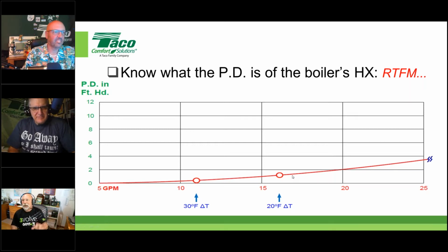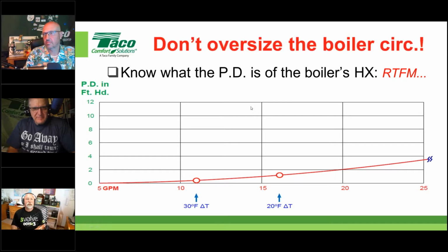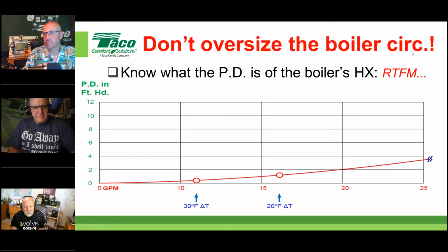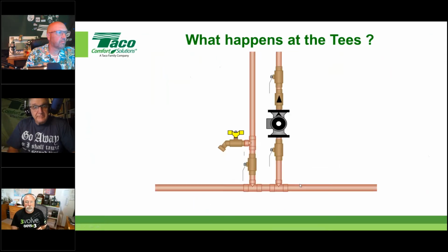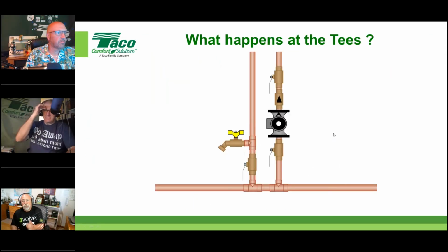There's all kinds of them out there, but what I want to emphasize more than anything is don't oversize the boiler circulator, and this is how you're capable of not doing that. You have to know what the resultant pressure drop is at given flows throughout the boiler's heat exchanger. So if you don't follow that, let's show you some pictures of what will happen.